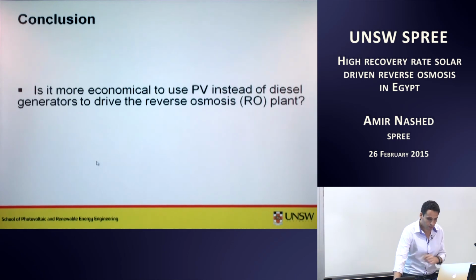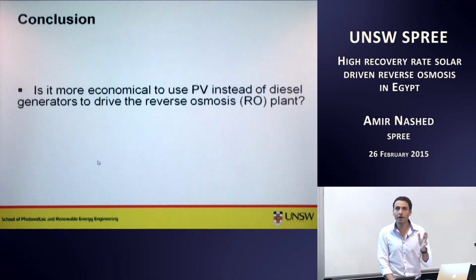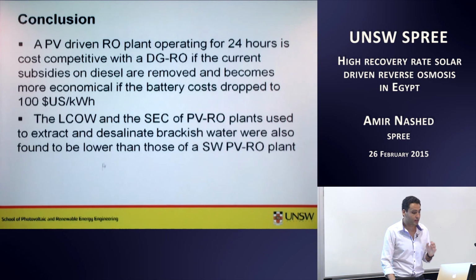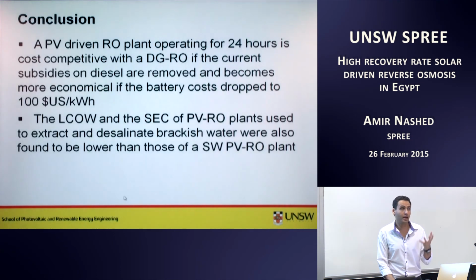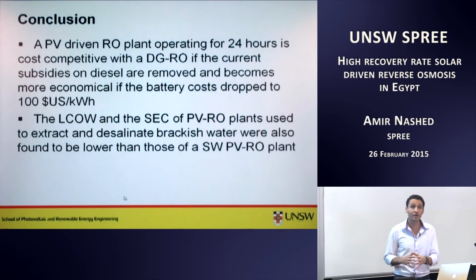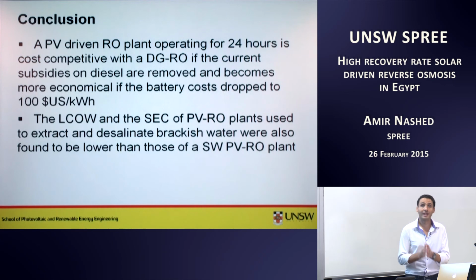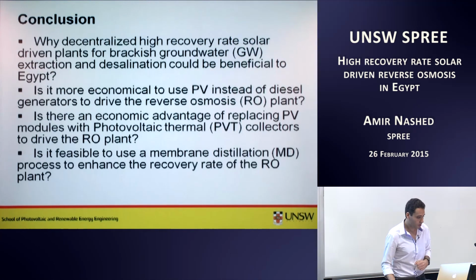Second, I asked: is it more economical to use PV instead of a DG generator to drive the RO process? With the current costs I used, it can be described as cost competitive, but if the battery cost drops to $100 per kilowatt hour, it will be clearly more economical. I also showed that the levelized cost of water for extracting and desalinating brackish water is actually lower than desalinating seawater.